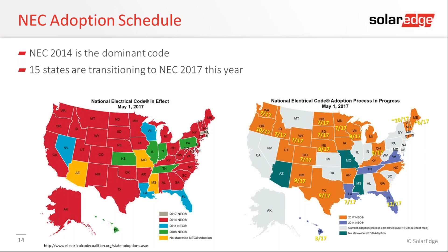In the US, we originally said you have to bring your rooftop voltage to less than 30 volts within 10 seconds. We extended the time range, and now it's 30 seconds. There's also a special effective date of no more than 80 volts on the rooftop, effective January 1, 2019, once initiation of a rapid shutdown has occurred. So if you're using string inverters now in the US, by 2019 you'll have to use some type of module level power electronics.